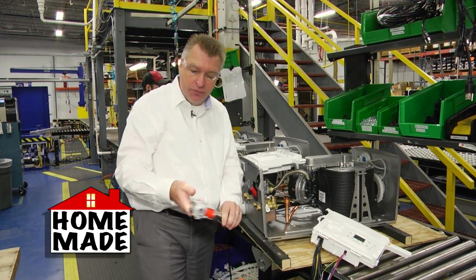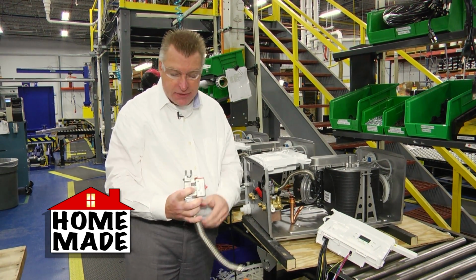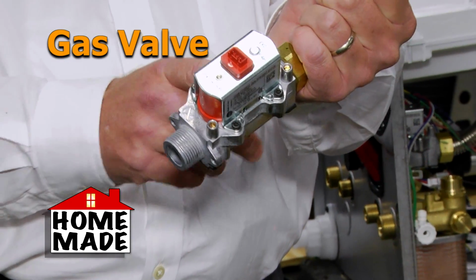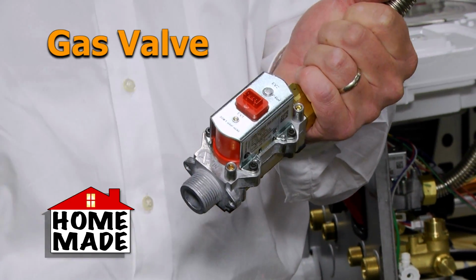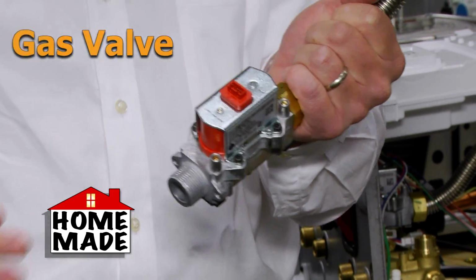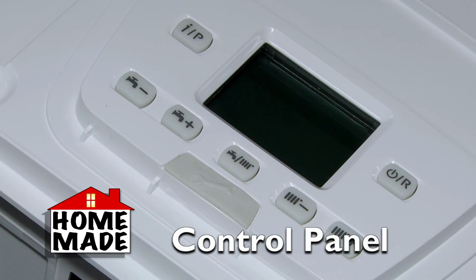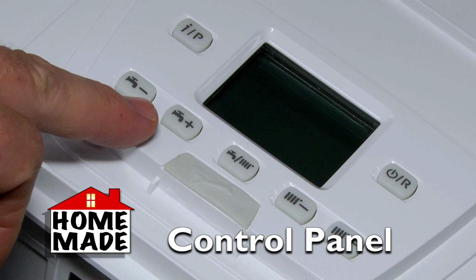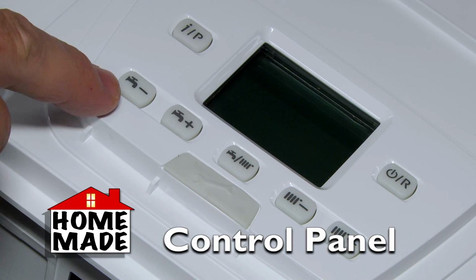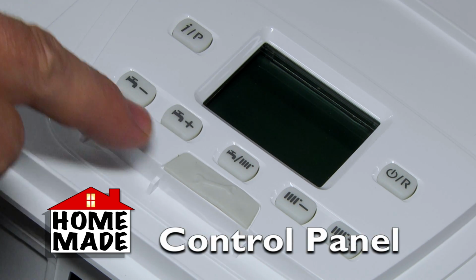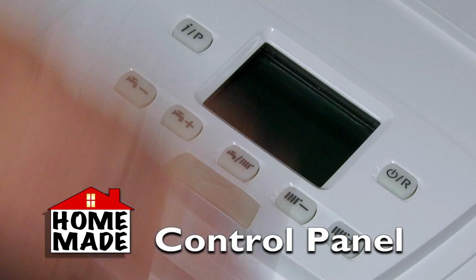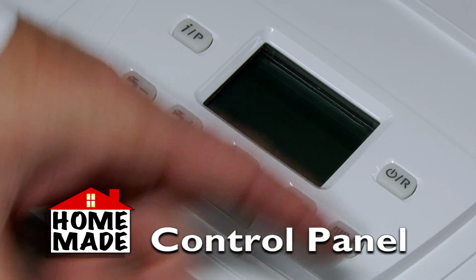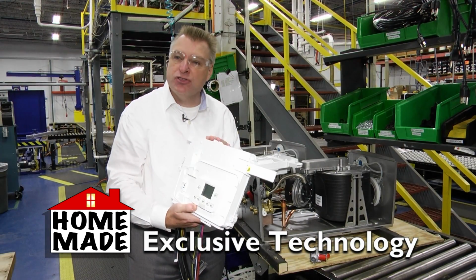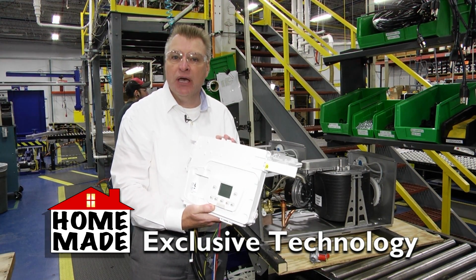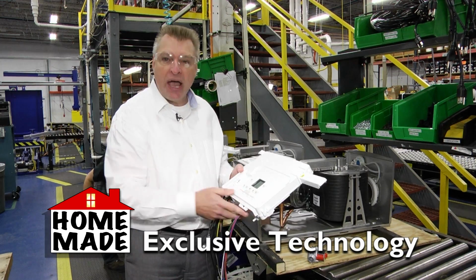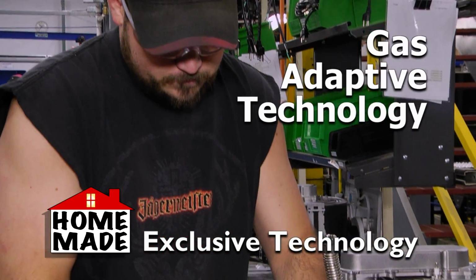Okay? The gas valve is very, very important to the boiler's operation because it controls the flow of the gas as well as the pressure of the gas. The control is controlling how much gas flow you want to the boiler based on your demand for temperature, whether it's the hot water for the house or the domestic hot water. Very important. The control actually recognizes the type of gas that you have going to the boiler. This is one of the only boilers in the U.S. market that has this technology. It's called gas adaptive technology. It recognizes whether a house has got propane or natural gas.